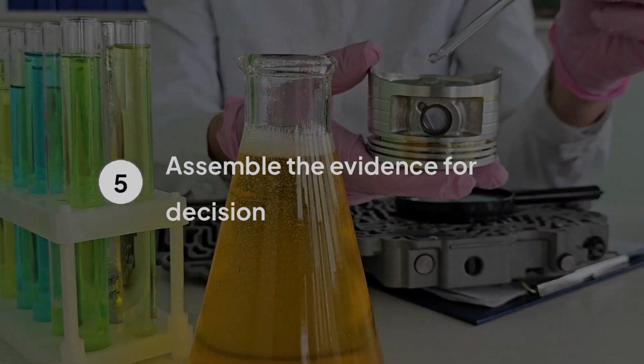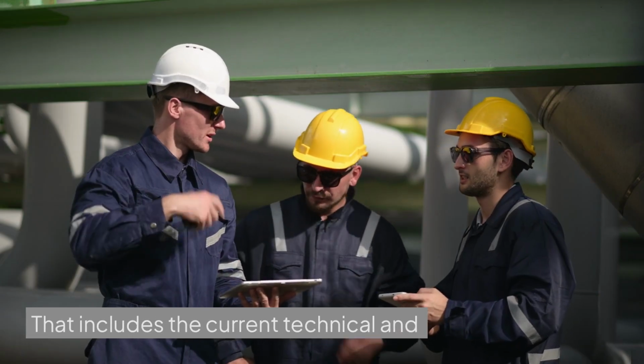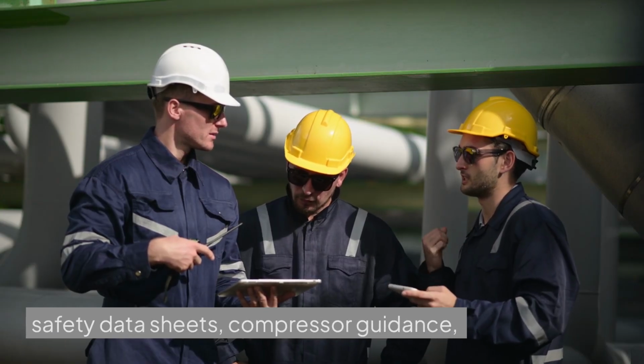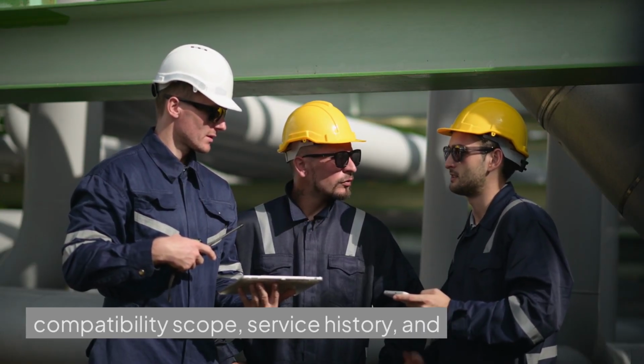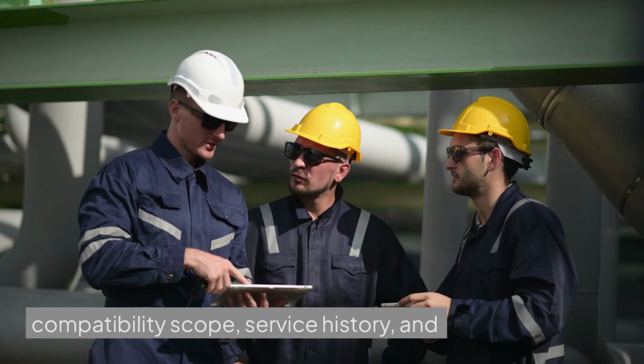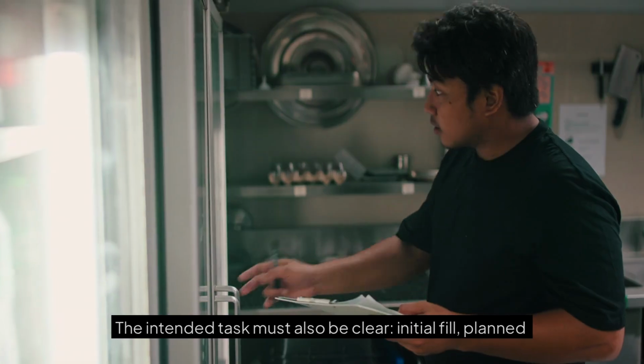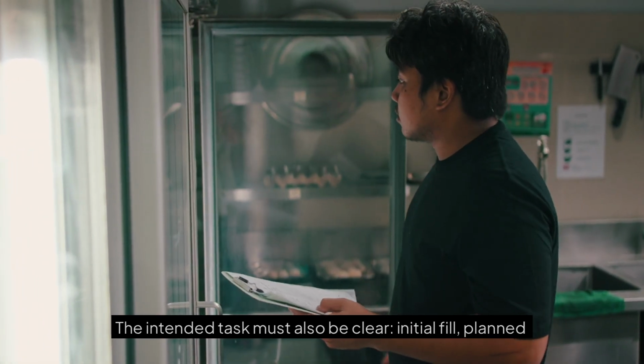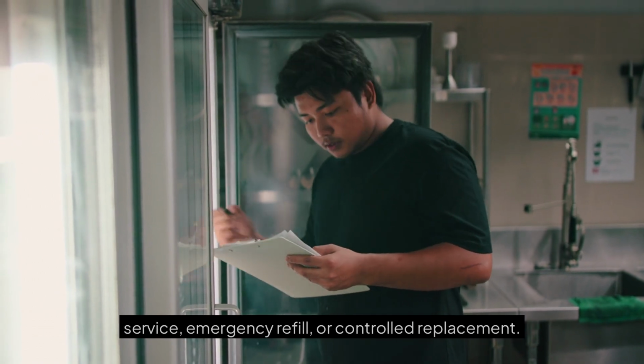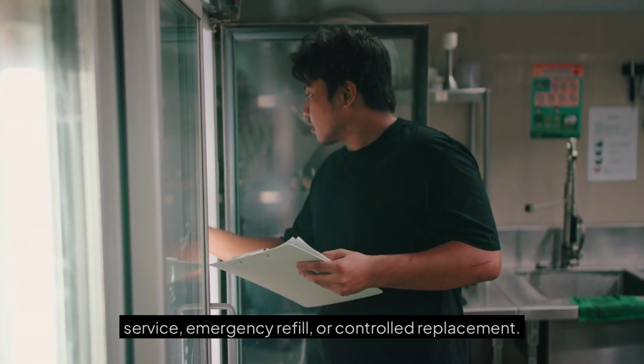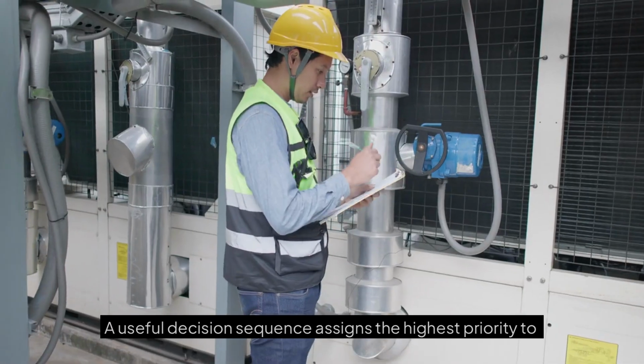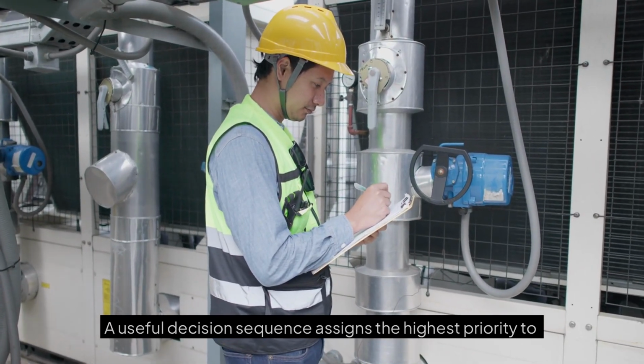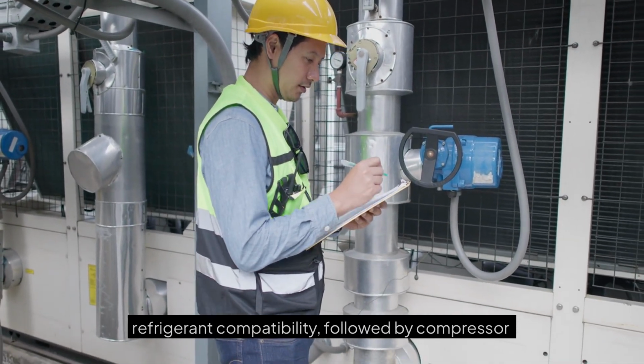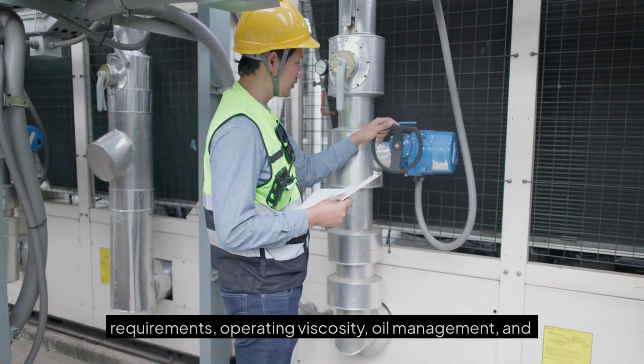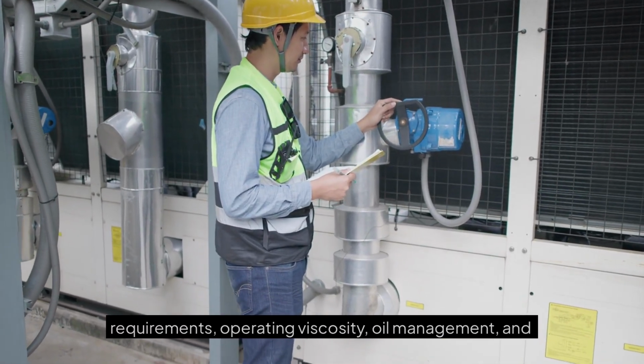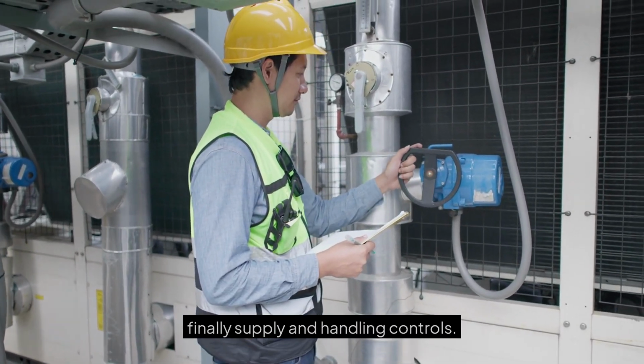Fifth, assemble the evidence. That includes the current technical and safety data sheets, compressor guidance, compatibility scope, service history, and records for the existing oil. The intended task must also be clear: initial fill, planned service, emergency refill, or controlled replacement. A useful decision sequence assigns the highest priority to refrigerant compatibility, followed by compressor requirements, operating viscosity, oil management, and finally supply and handling controls.